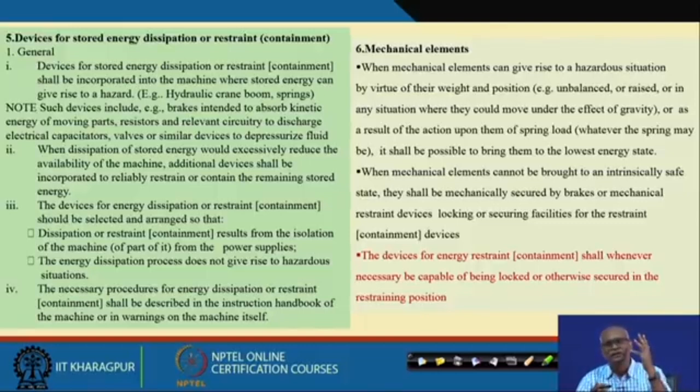There are many things: energy dissipation of flywheels, energy dissipation of pressurized fluids. I have seen cases where people have died while dissipating energy, especially in hydraulic circuits. If you want to release the high pressure in a high pressure circuit, that high pressure liquid hits people, and they get injured and die. So there are procedures for how to dissipate the energy.